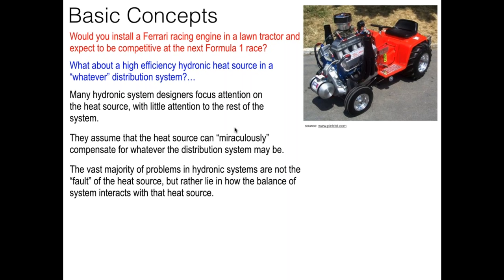A classic example: take a low temperature heat source like a geothermal heat pump. A typical standard water-to-water geothermal can supply about 120°F as its maximum. If you connect that to a system with baseboard sized around 180°F water temperature, you're going to have immediate problems. The baseboard simply can't get rid of the heat at low water temperature, and the heat pump can't get rid of the heat either. The heat pump is going to short cycle or trip out on a high refrigerant pressure safety. It's really about compatibility between the heat source characteristics and the distribution system.